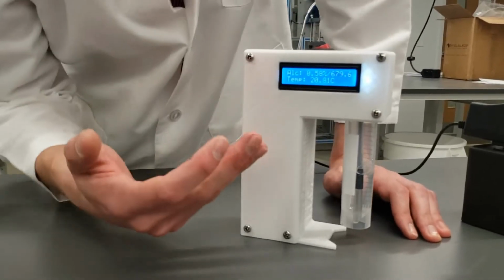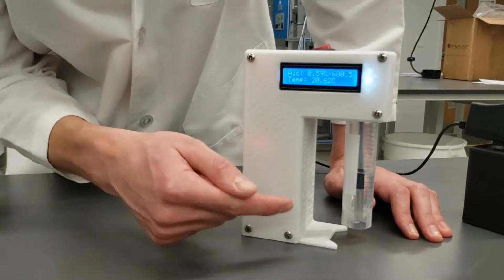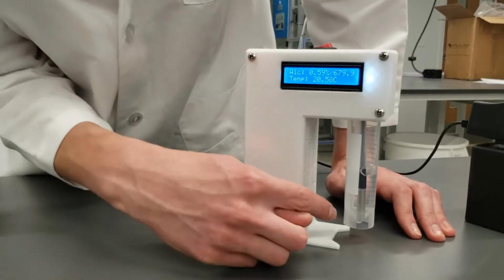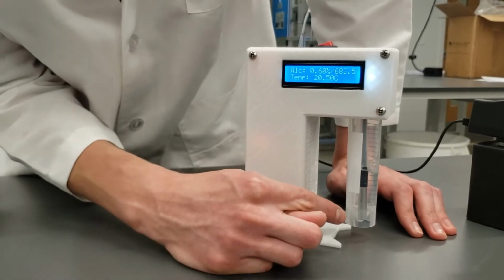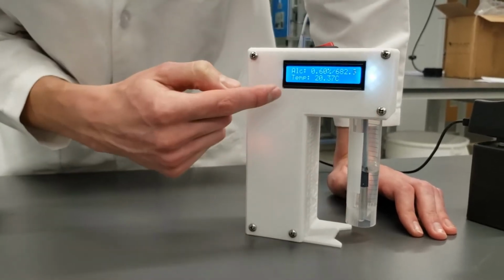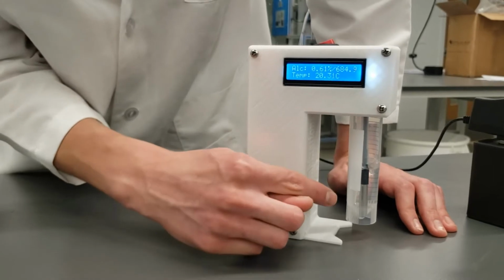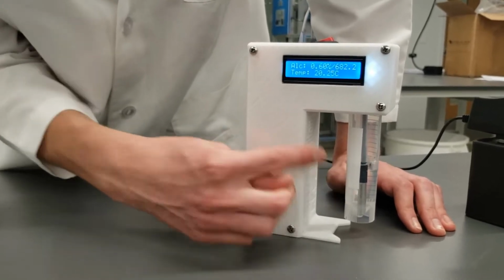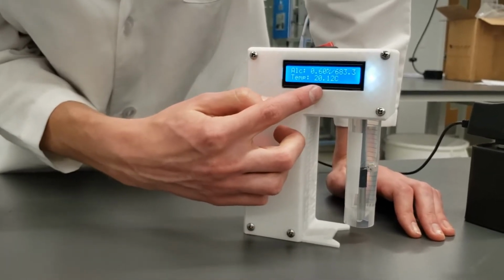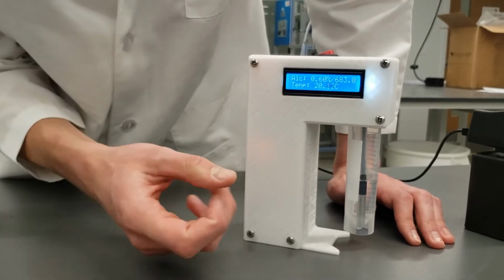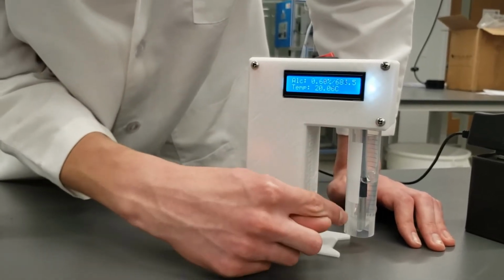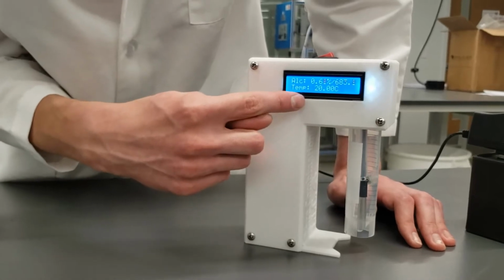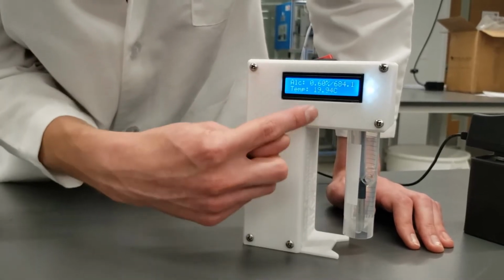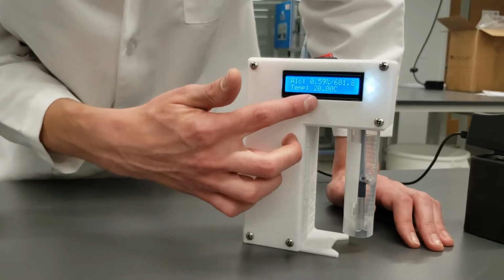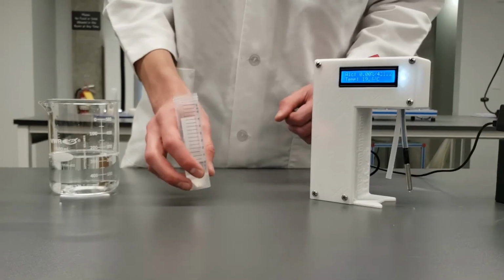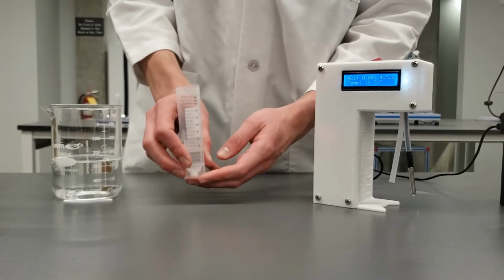So the way that we fix this issue is we're either going to heat or cool the sample. So if with the 0.5% alcohol standard it reads higher, like in this case, that means we know that the calibration temperature must be lower than 20 degrees C. But if the standard reads lower than 0.5%, then we know that the calibration temperature must be higher than what's reading on the screen.